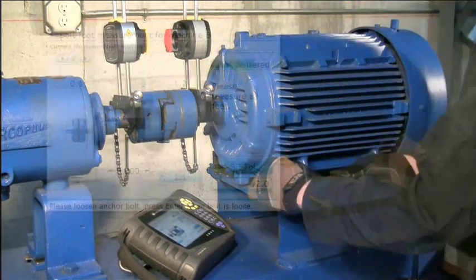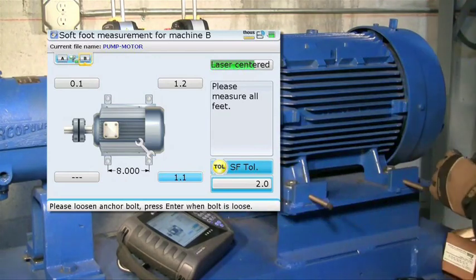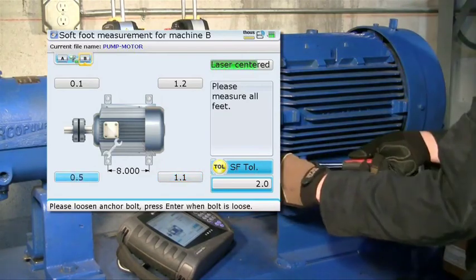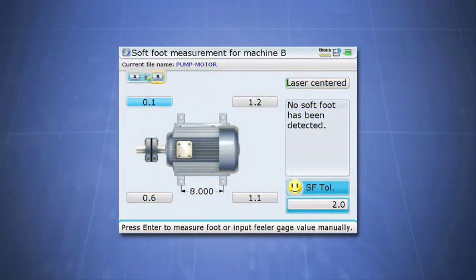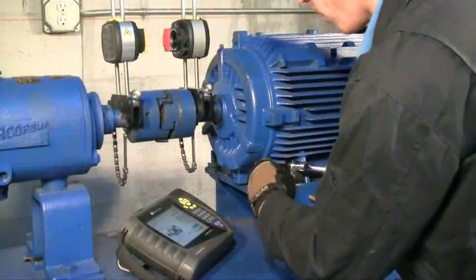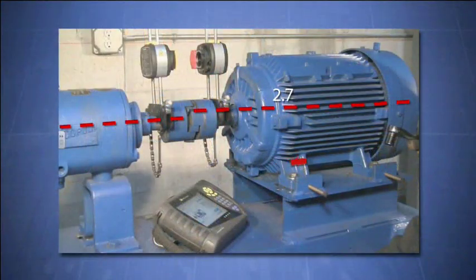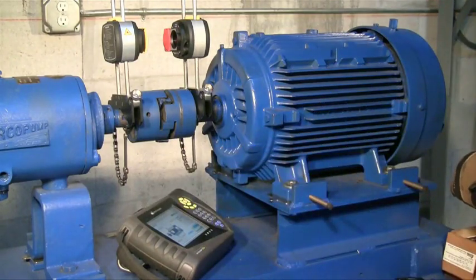Let's now begin our final softfoot check. Simply loosen one hold down bolt with the other three feet tight and let the ROTALIGN Ultra measure the shaft deflection. Then re-tighten the bolt. Move to the next bolt and repeat this process for the remaining bolts. The numbers displayed are the calculated values for the shaft movement at each hold down bolt position. If your displayed values are less than two mils, you have no significant softfoot and you can proceed with the rest of the alignment. If your softfoot values are greater than two mils, then you have a softfoot that needs to be addressed. Be aware that the numbers are not necessarily the actual gaps under the machine feet — we are measuring the effect of that particular foot on the shaft deflection, not the actual gap.